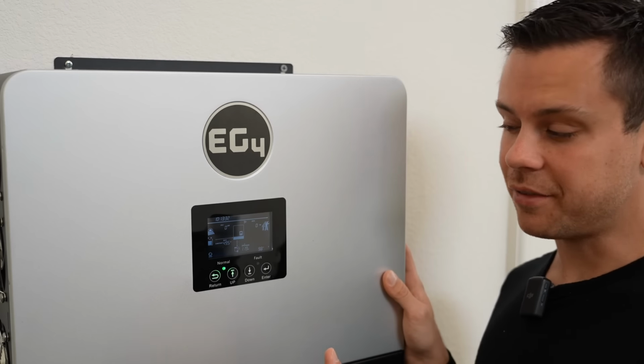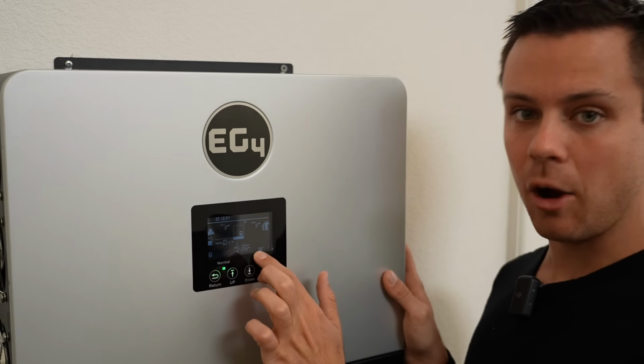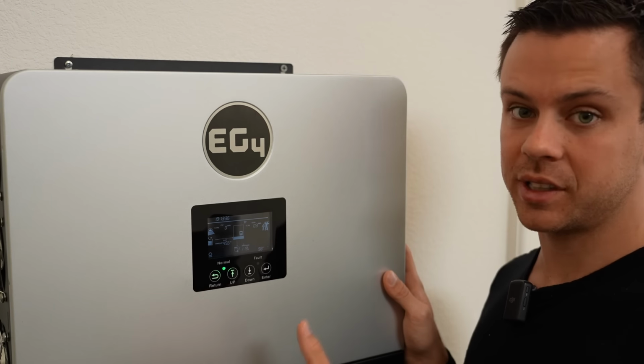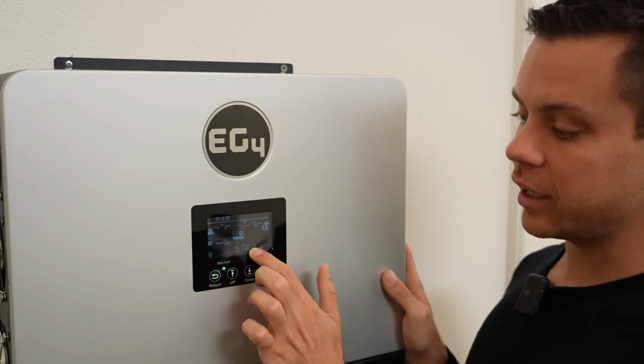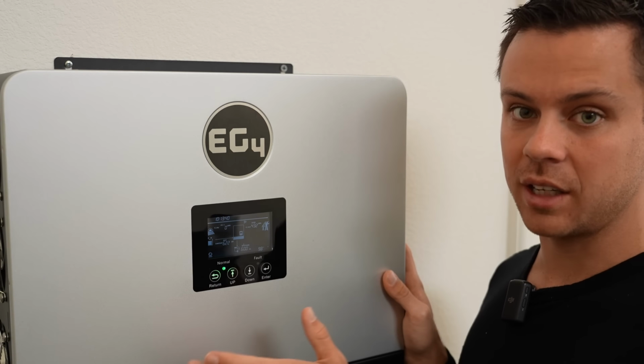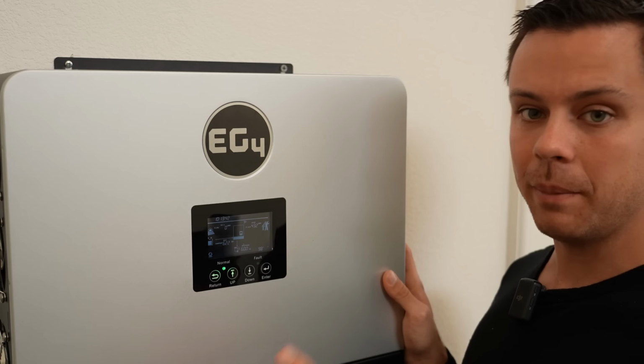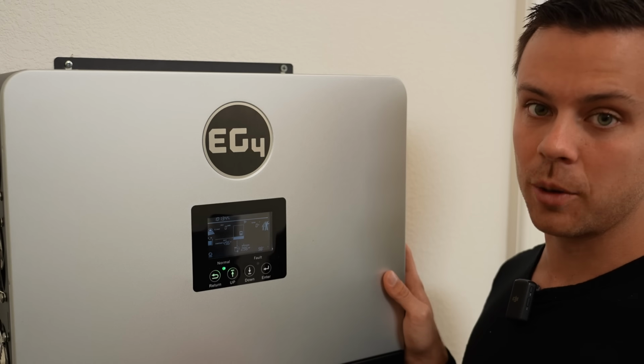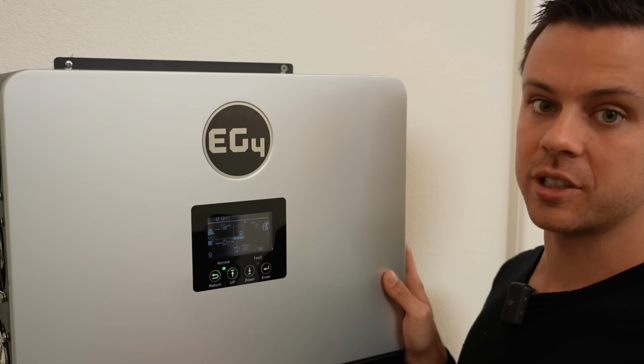Now the efficiency figure from the battery to the AC output is off by 1%. Typically, if I use the screen, it will say it's 95% efficient, but if you measure it with a meter, you'll get 93 to 94% efficiency, which matches the spec sheet.